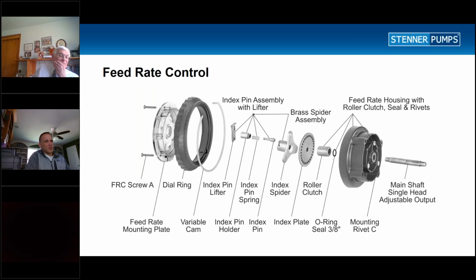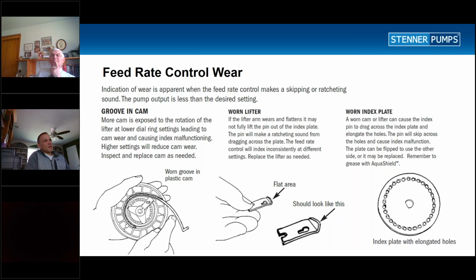And this gives you a little bit more background on the exploded view. So when you're servicing the feed rate control, if you see that the index plate has worn or rounded holes, that's a sure sign that you would need to either replace or flip the plate over. A flat end on the bottom of the lifter will create issues. And in many cases, what I see most often are worn index plates and grooves in the cam from that lifter running on the cam. Usually I'll see this if a pump's running at a low setting, somewhere in that 1 to 5 range frequently.